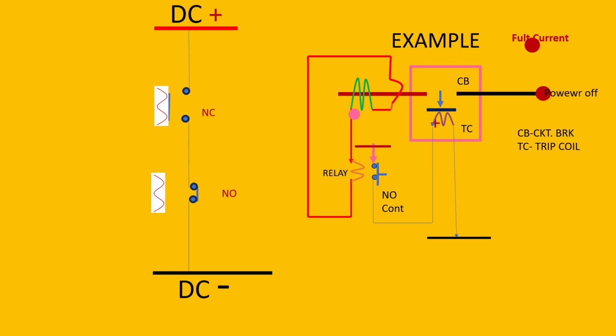The current will pass through the relay, and due to this fault the relay setting will attract the normally open contact. The relay coil will be energized and bridge the two normally open contacts, and DC positive will be extended to the trip coil of the circuit breaker, where one end is positive and the other end is permanently given negative of the CB trip coil. So the coil will be energized and the circuit breaker will open, making the circuit dead. During any fault, the circuit breaker will open.